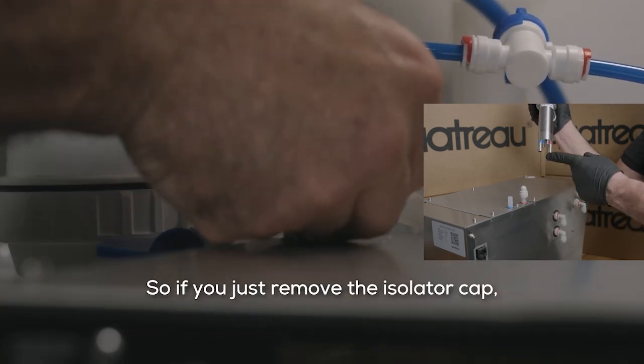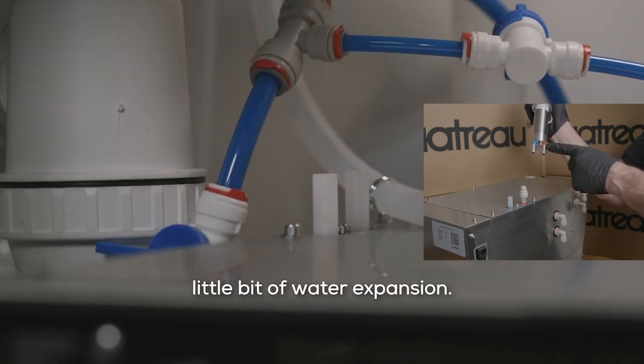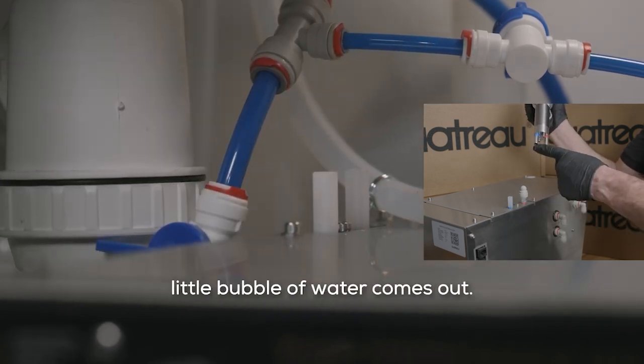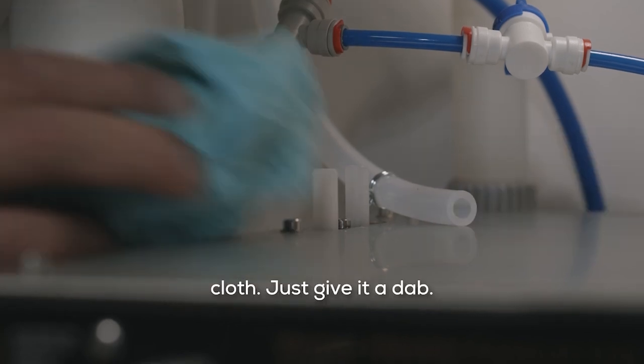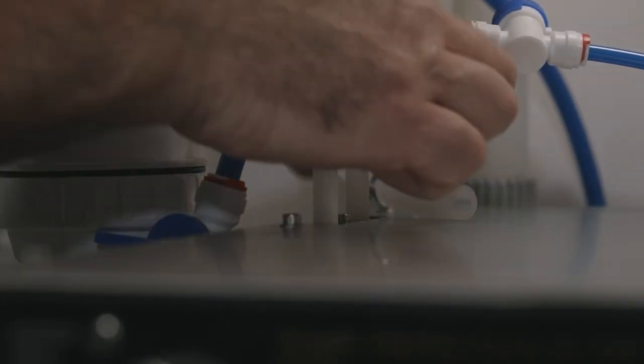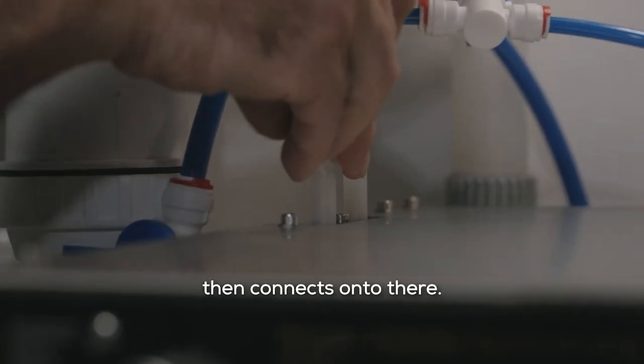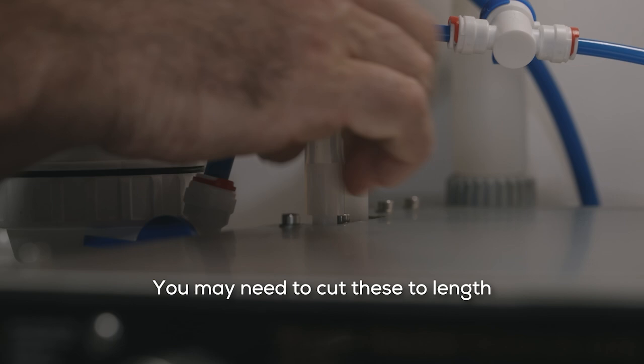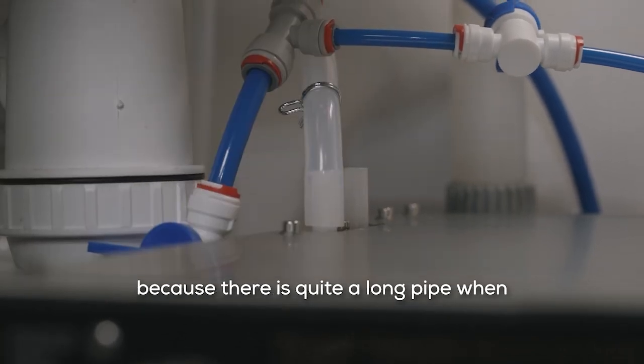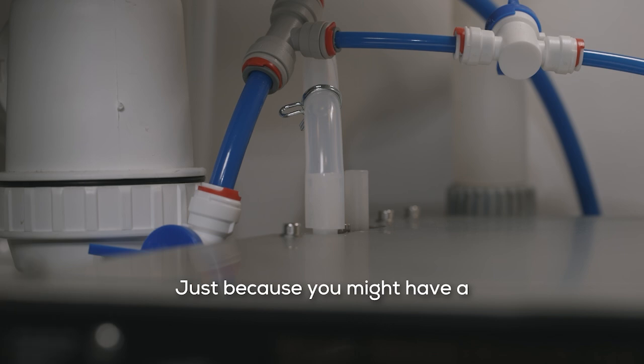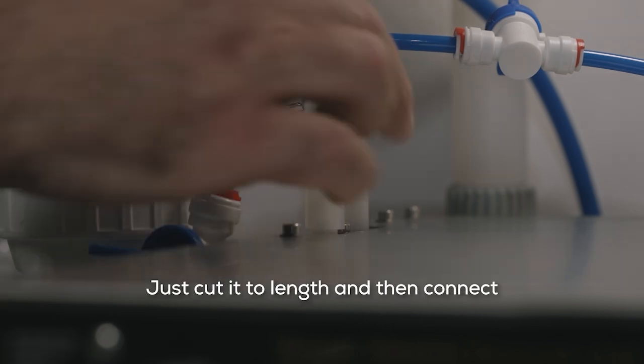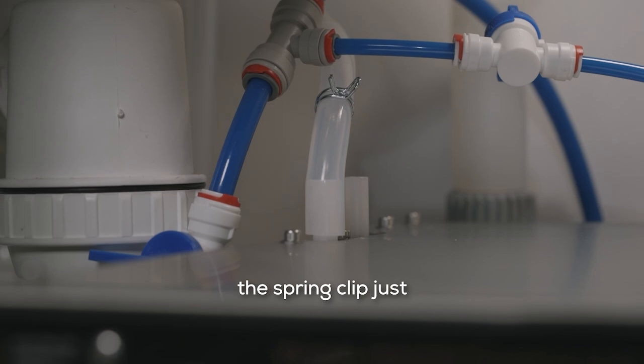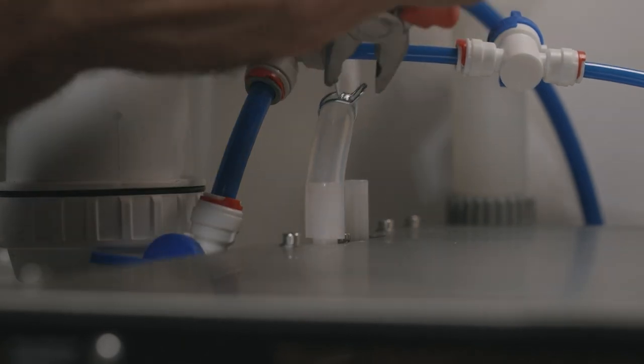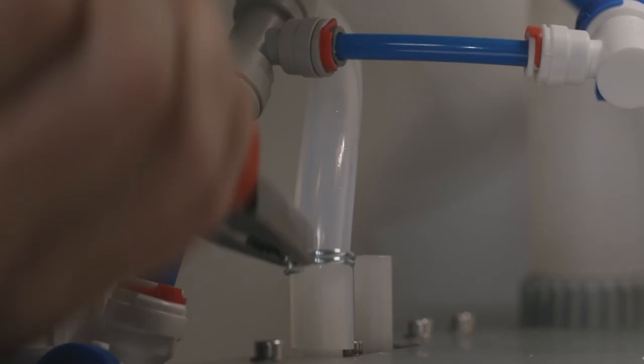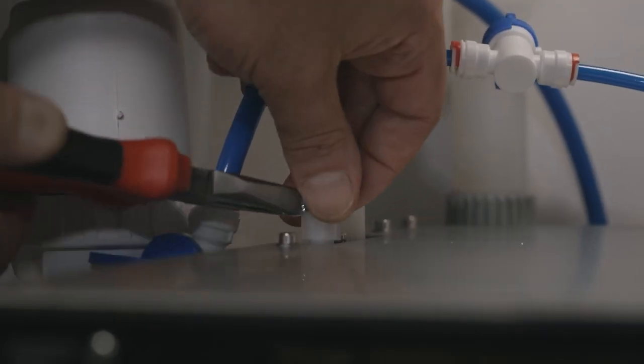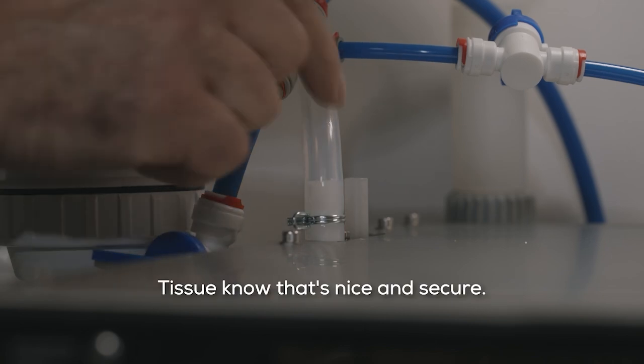So if you just remove the isolator cap, there may well be a tiny little bit of water expansion, so don't panic if just a little bubble of water comes out. Just catch it with a cloth, just give it a dab. Your silicone pipe then connects onto there. You may need to cut these to length because there is quite a long pipe when they come out of the packet, just because you might have the machine in a different place. Just cut it to length and then connect the spring clip just to hold it all in place. Just so you know that's nice and secure.